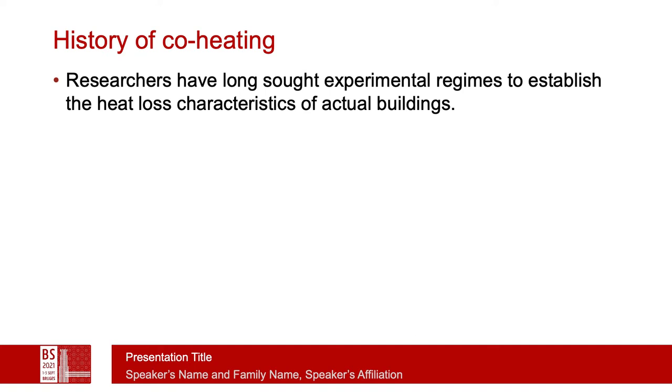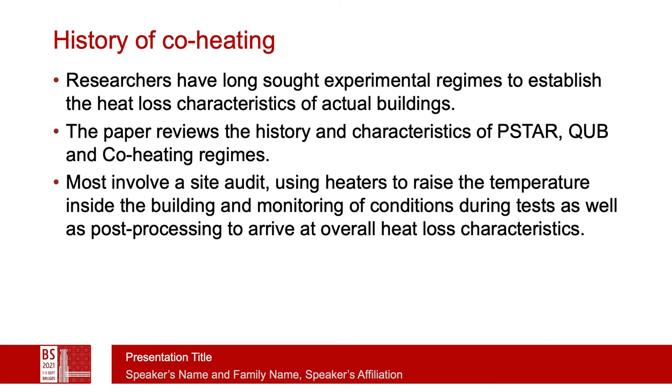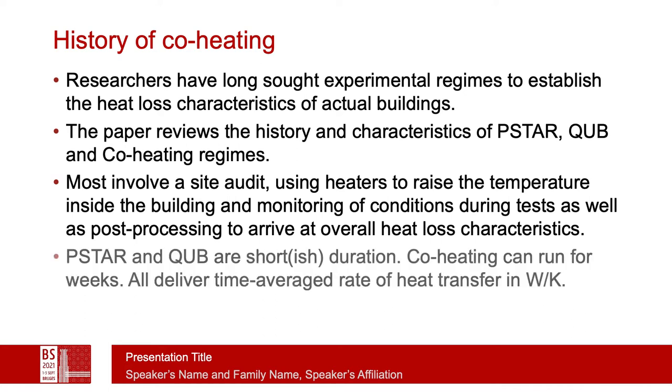Co-heating has gone on for a considerable amount of time because there has been a continual need to establish actual heat loss characteristics in buildings — the gap that is often talked about. In the paper, we review the history and characteristics of several methods, including PSTAR, QUB, and co-heating. Most of these involve a site audit and the use of heating or cooling devices to explore how much heat is necessary to maintain a particular set point under varying outside conditions. Post-processing is required to arrive at overall heat loss characteristics.